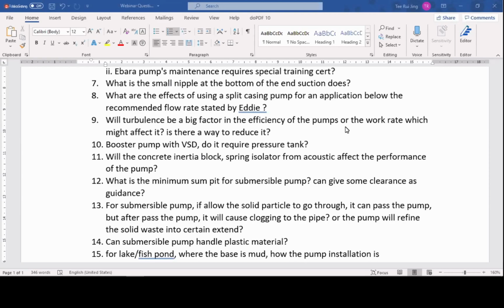So what will happen is that, you know, water also needs a very good laminar flow. But an elbow, if it's a very sharp elbow, can cause turbulence of the water when it goes into the pump, and that will increase the NPSH of the pump, which means it will actually cause poor suction of the pump, and that may affect the pump operation. Well, not to a very big degree, but it will affect in some way. And again, if it's a system design problem, then eventually the pump will lose suction.